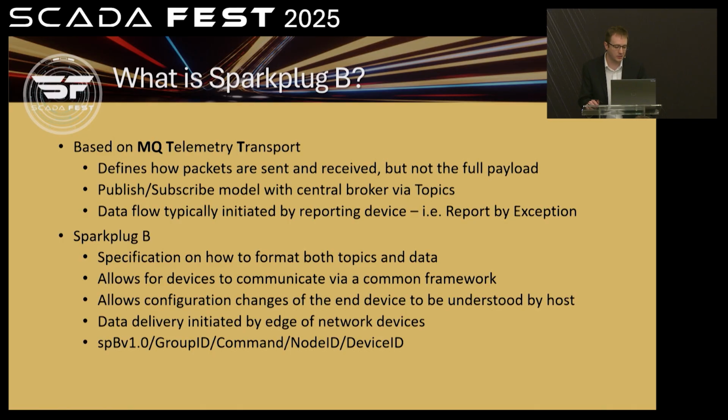A node ID, which identifies basically the device that's doing the publishing. Typically, at least that's the way we've implemented VT-SCADA, a node is the one that actually sends the messages, and devices live under the node and tell the node, hey, I have a message for you to send for me, and that's where you would get a device ID part of your message. So we've broken it up that way.